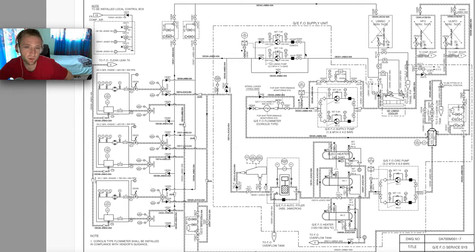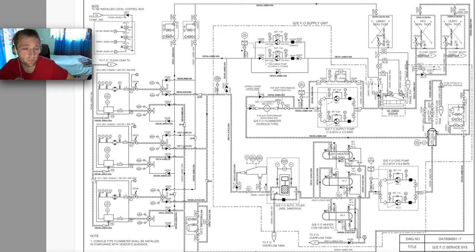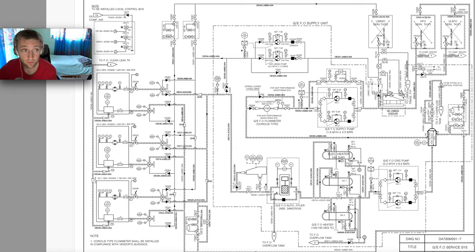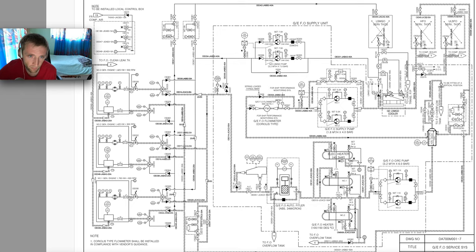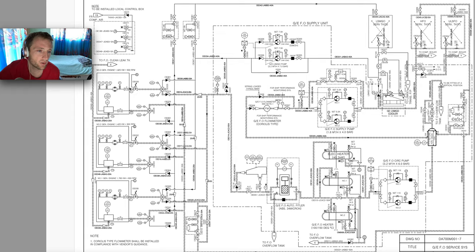These pumps will deliver our diesel here in the separate line. The only thing we need to open is the inlet and outlet of the diesel. All the other valves — the pressure regulating valves and the return back — we need to verify they are open. It's a separate system, a very nice and quick system for changeover. In that vessel, all the valves were always open on standby — every return and suction valve. So what we did: in the event of a blackout, we only opened the inlet and outlet valve of the diesel generator and directly started this pump.